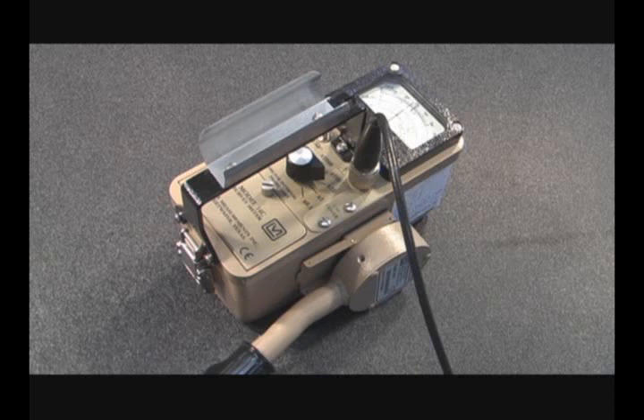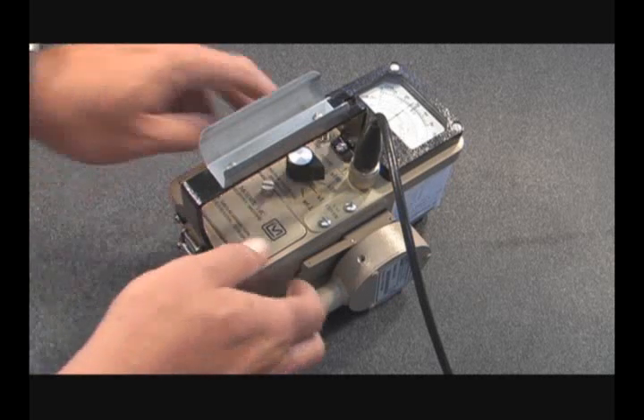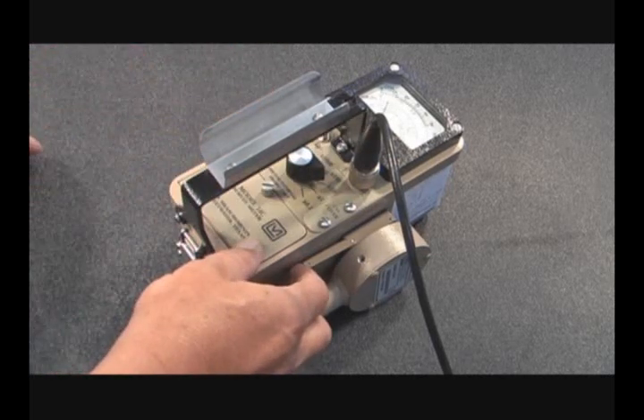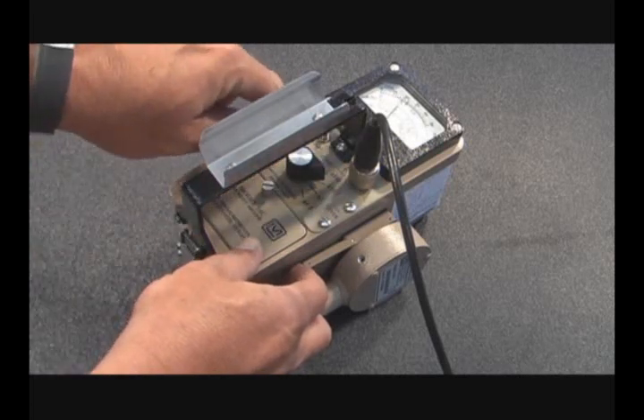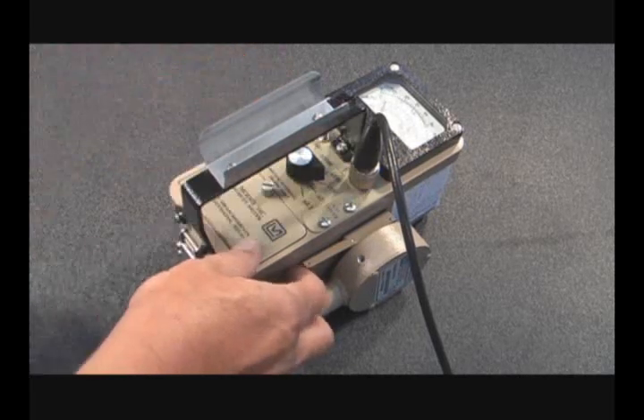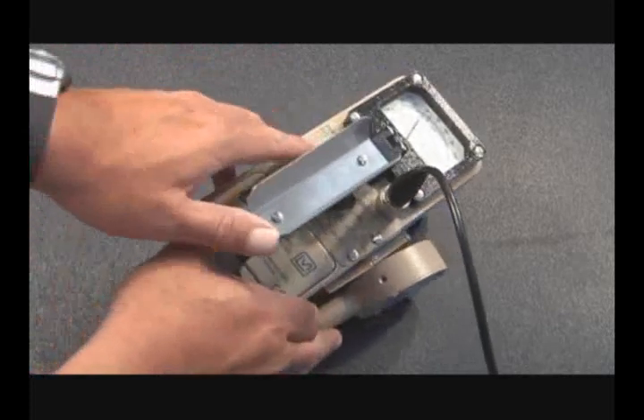The fast response position of the fast flow switch is the normal position for emergency response work. Check the meter reset function by depressing the reset push button switch and ensuring that the meter needle drops to 0. When released, the needle should return to the current reading.